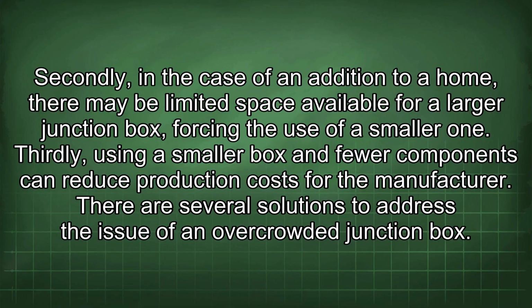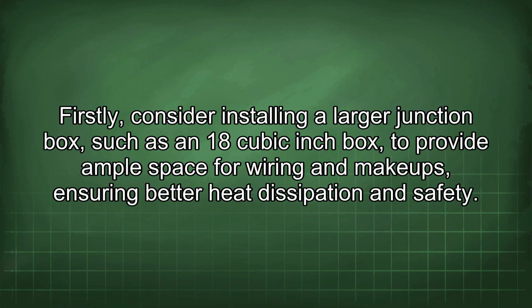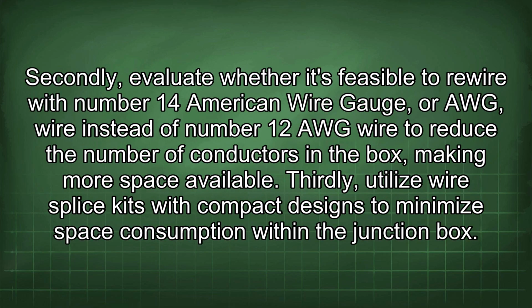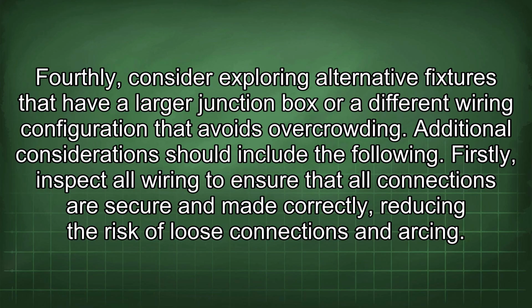There are several solutions to address the issue of an overcrowded junction box. Firstly, consider installing a larger junction box, such as an 18 cubic inch box, to provide ample space for wiring and makeups, ensuring better heat dissipation and safety. Secondly, evaluate whether it's feasible to rewire with number 14 American wire gauge, or AWG, wire instead of number 12 AWG wire to reduce the number of conductors in the box, making more space available. Thirdly, utilize wire splice kits with compact designs to minimize space consumption within the junction box. Fourthly, consider exploring alternative fixtures that have a larger junction box or a different wiring configuration that avoids overcrowding.